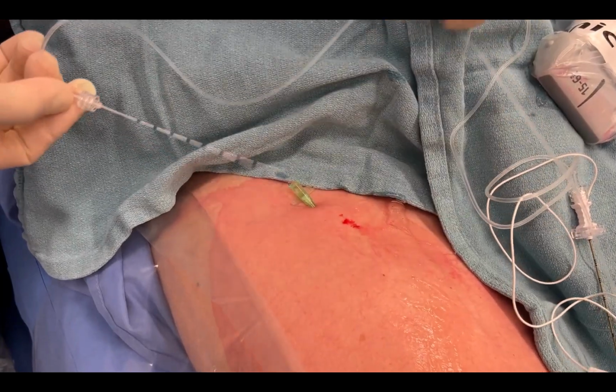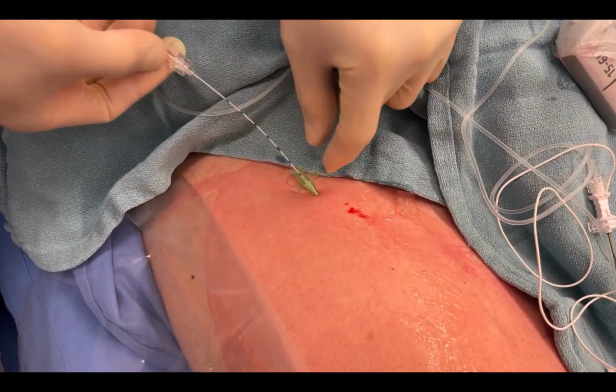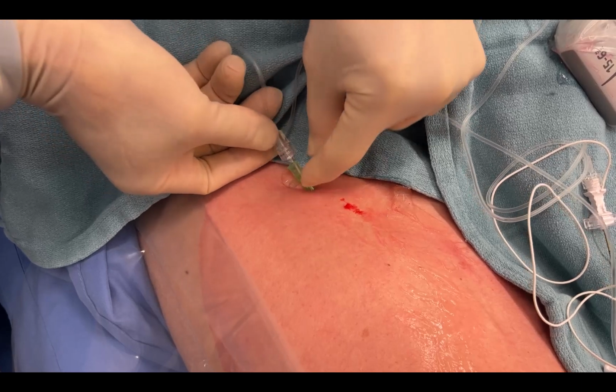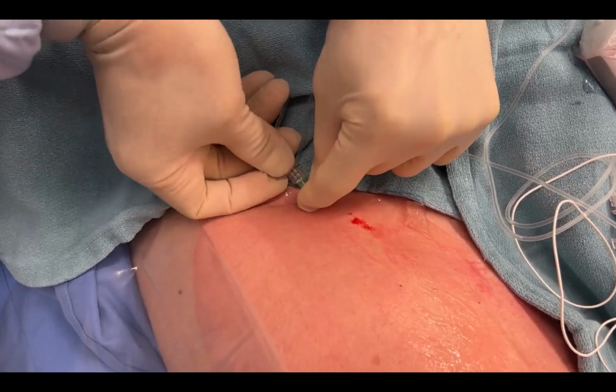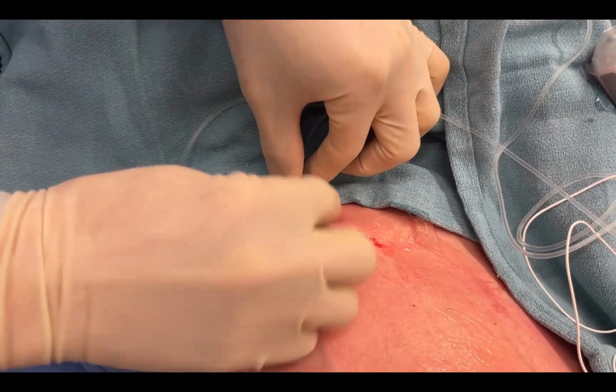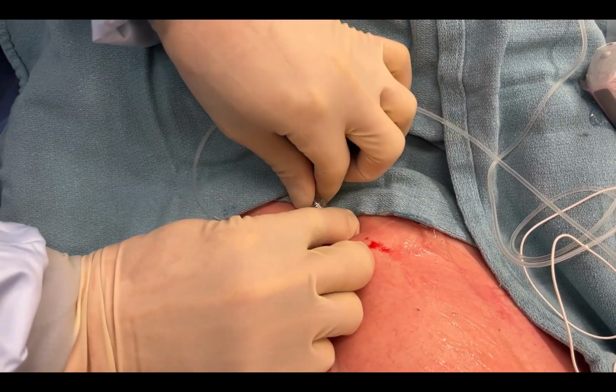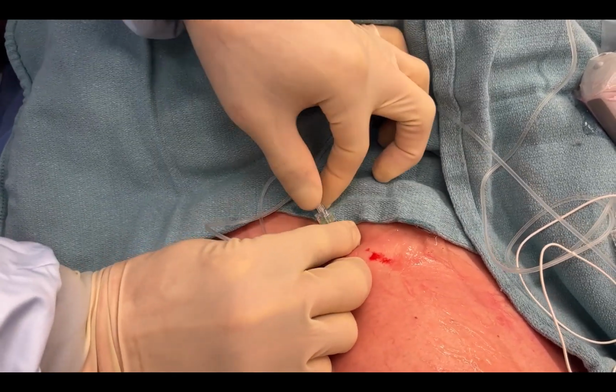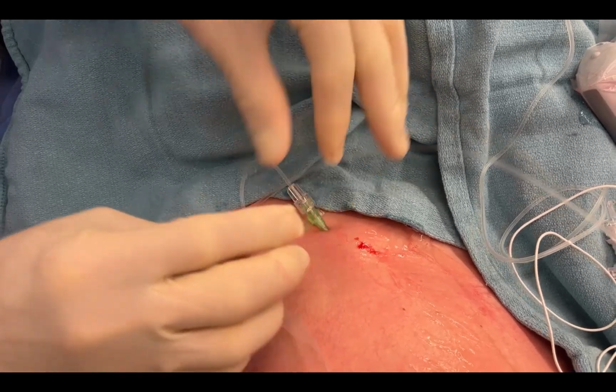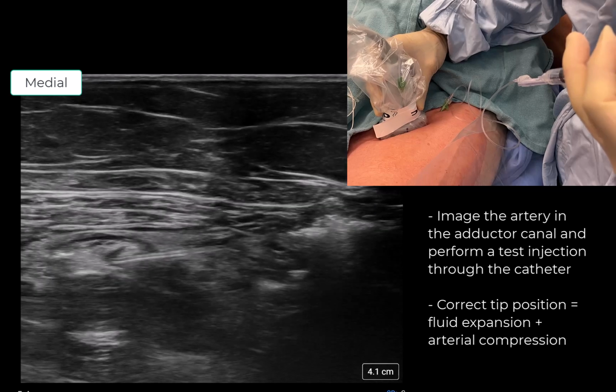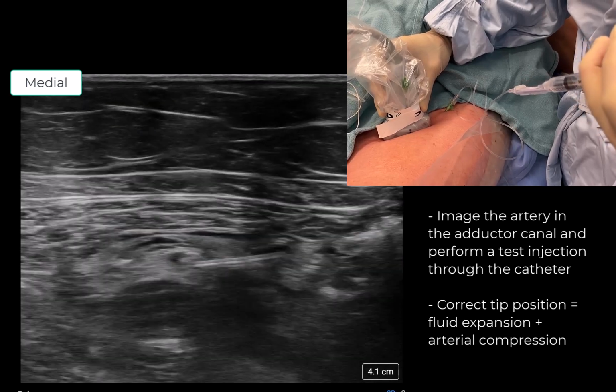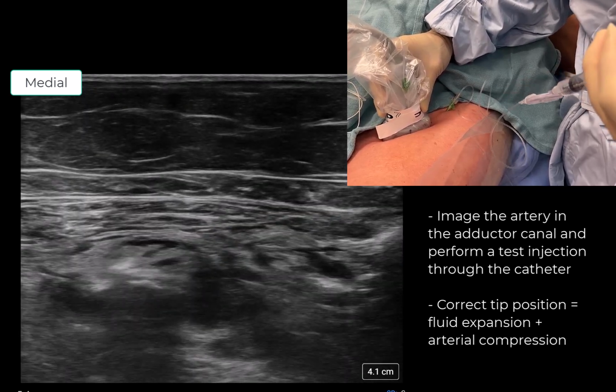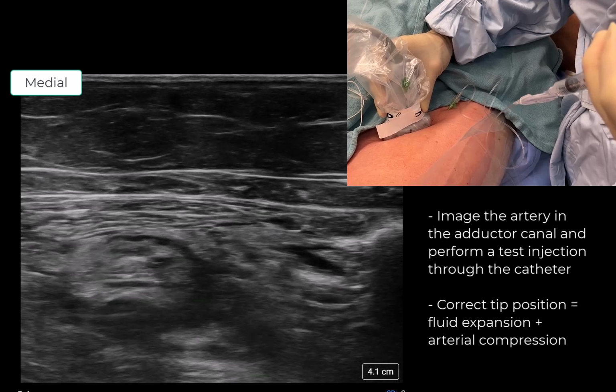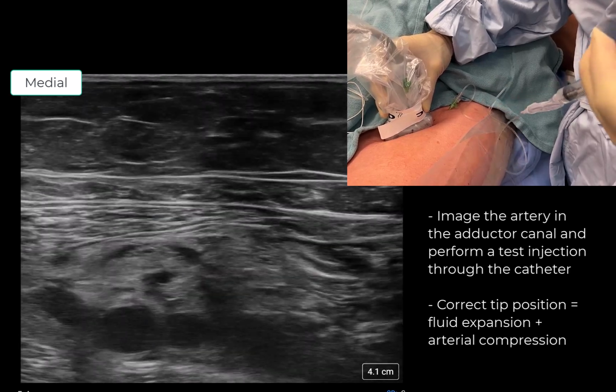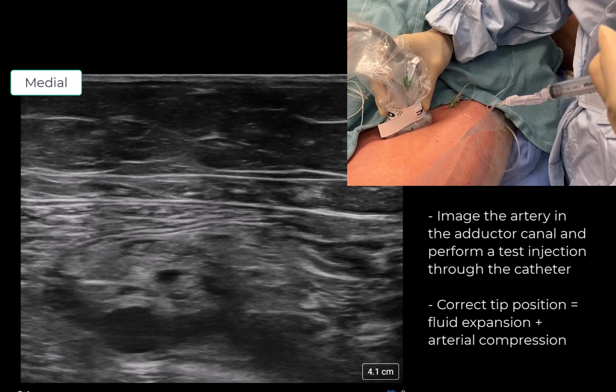Insert the fluid-primed inner catheter and thread it into the introducer cannula. There should be no resistance to advancing it up to the hub of the introducer. If there is resistance, the introducer cannula tip may be kinked. If so, carefully withdraw the introducer slightly to see if this solves the problem. Ultrasound imaging is then used to verify catheter placement, and test injection is performed to verify spread within the compartment. Arterial compression with injection is again a useful confirmatory sign.